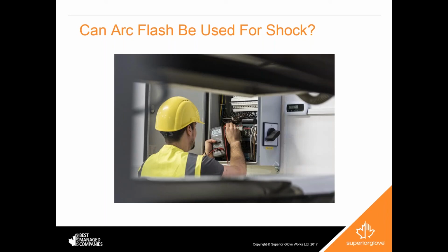Great. And sort of along that same vein, what is the minimum arc flash rating for PPE for a category? Yeah, for sure. Category 0, which is considered the type of PPE you need to wear for that, is not really a category for arc flash, but it would be your 1.2 calories per centimeter squared, and you'd have to wear at least an untreated cotton for that. So that's the minimum calories per centimeter squared for the onset of a second degree burn.